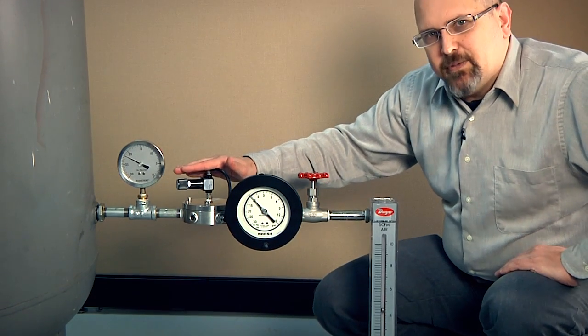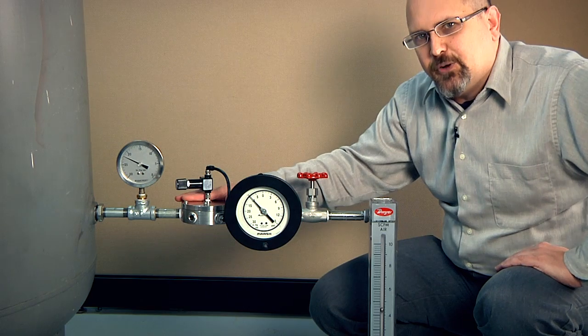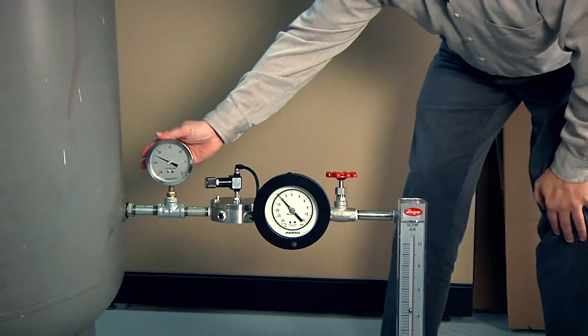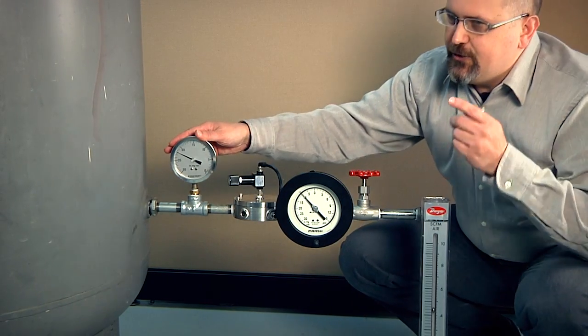Now there's one more thing about using a regulator, because it's a true active regulator, an active control device. I can actually have the system vacuum vary as well. And we're going to do that right now.